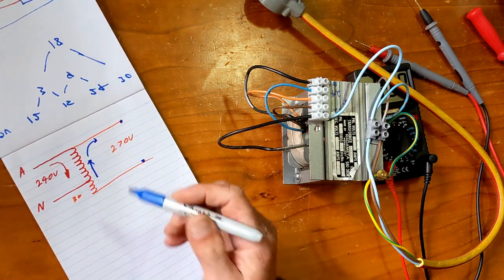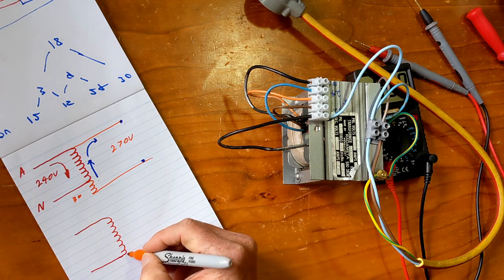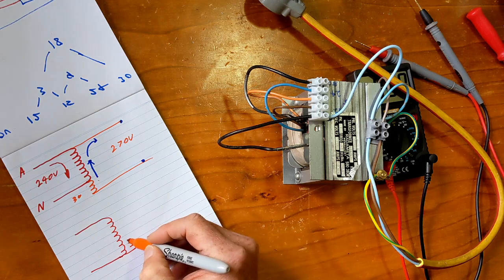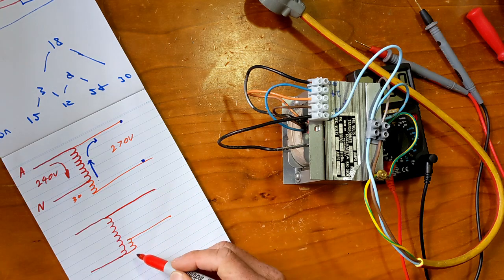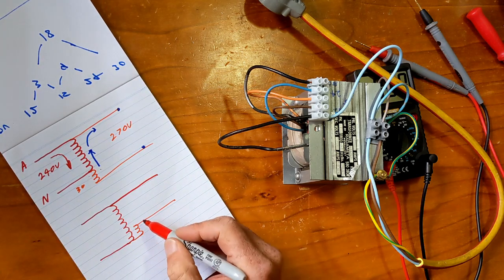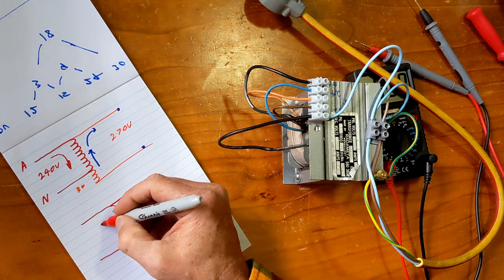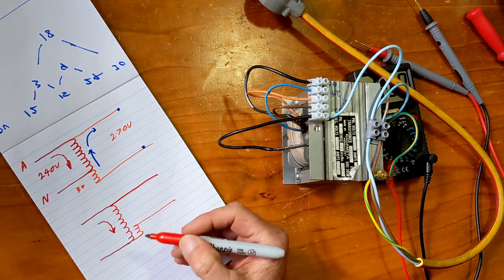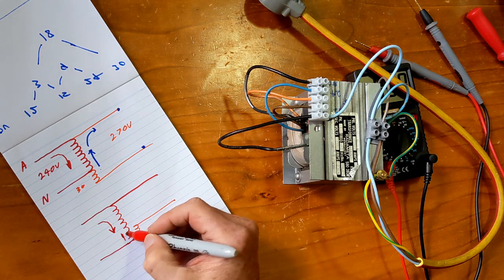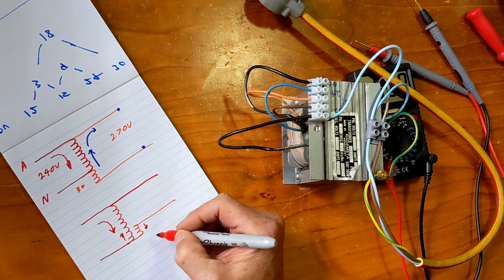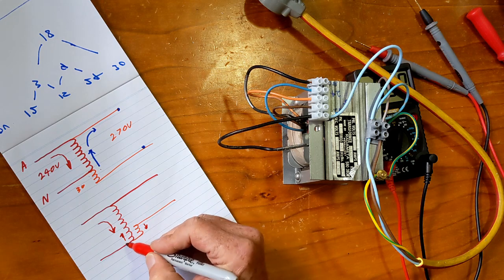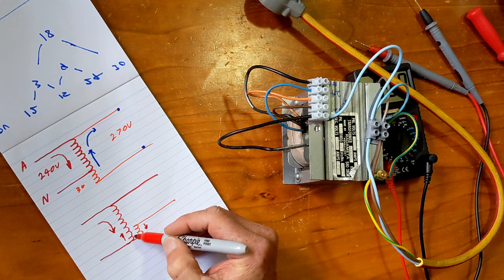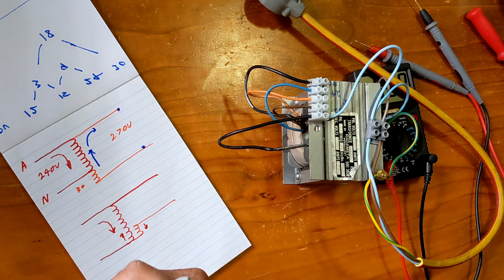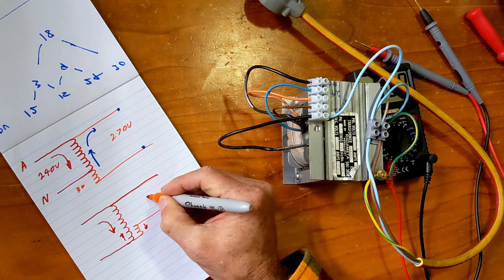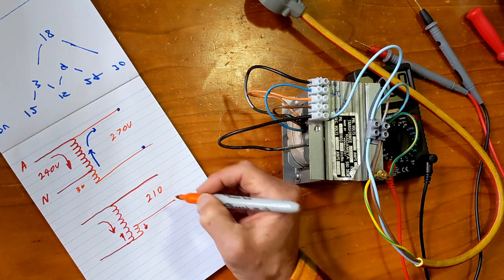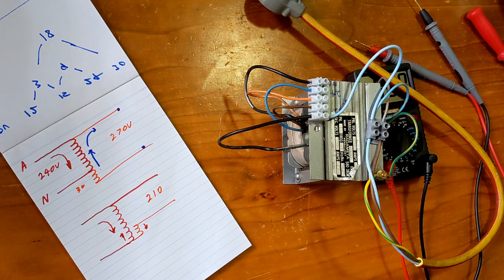If I switch these around the wrong way, it might help to think of it like this. This is essentially the same drawing, except that these are in the wrong direction. So what's happening is voltage is applied to these. That induced voltage that's going back this way, on these ones is going this way, cancelling out the effect of all these turns. So although I've got the two windings connected in series, I'll end up with a lower voltage here, 210. Just for the fun of it, let's have a look at that.